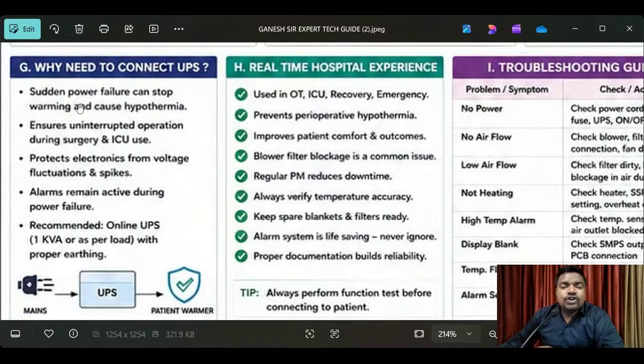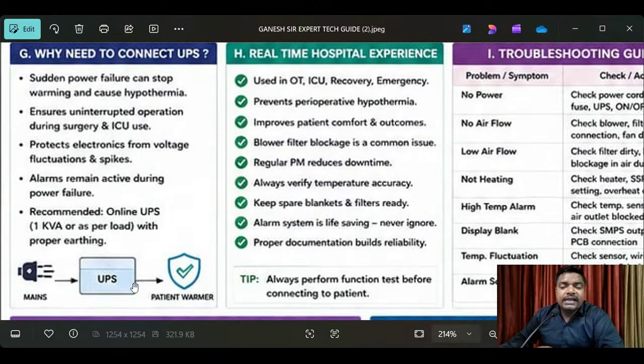Sudden power failure can stop warming and cause hypothermia. A UPS ensures uninterrupted power during surgery and ICU, protects electronics from voltage fluctuations and spikes, and keeps alarms active during a power failure. Recommended: online UPS, 1 kVA or as per load, with proper earthing. These are the very, very important main UPS and patient warmer, because whenever electrical issues occur, we cannot imagine them. That's why we have to protect the equipment by using UPS connections.